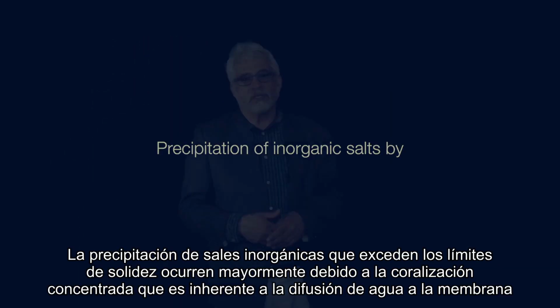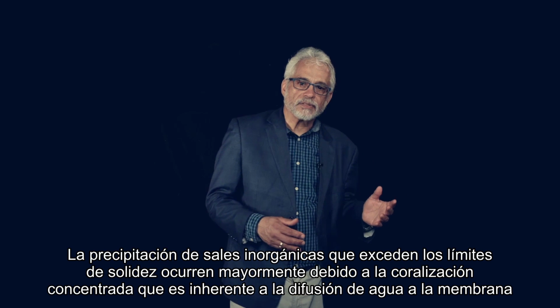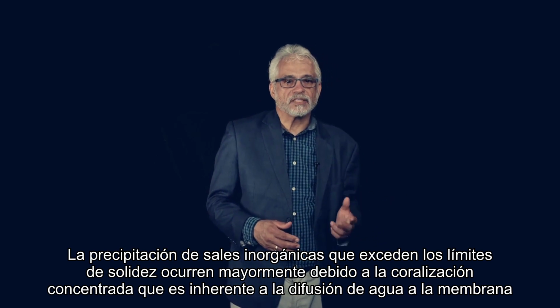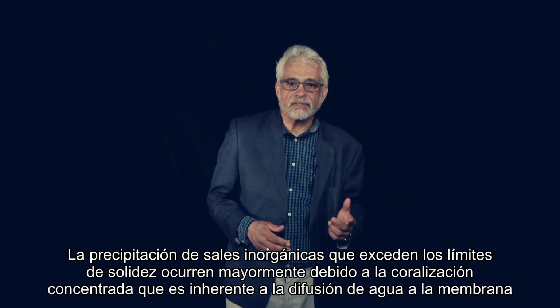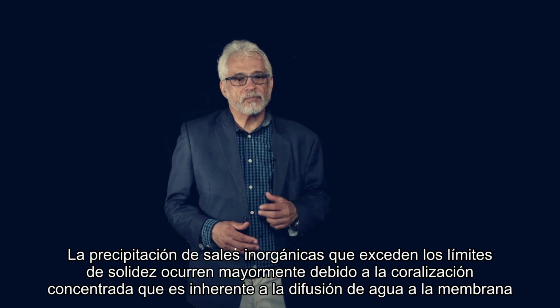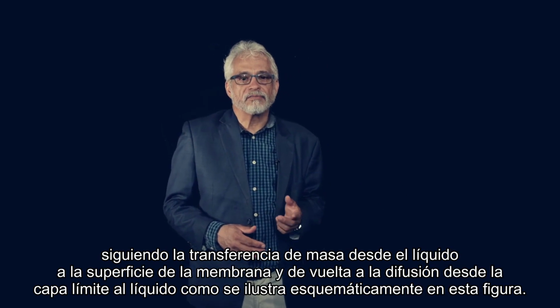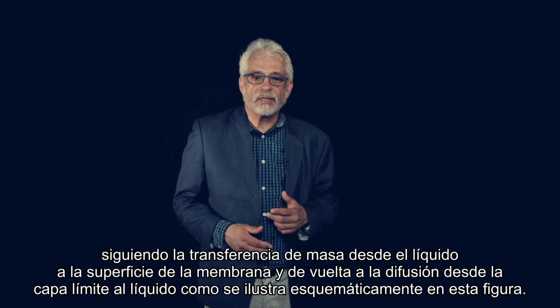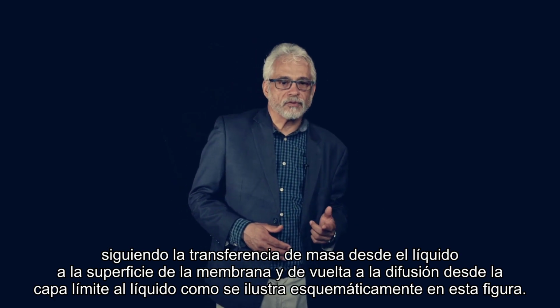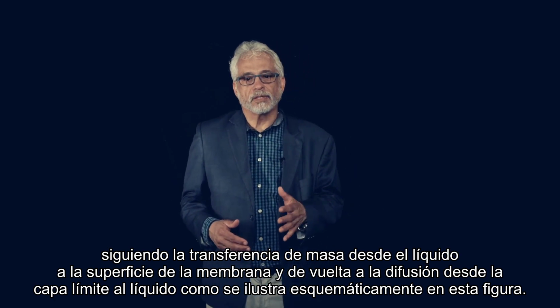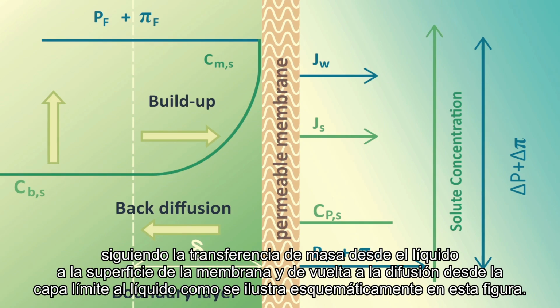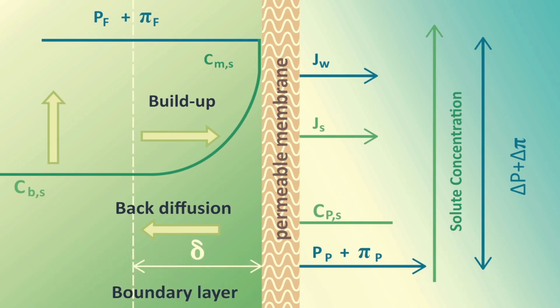Precipitation of inorganic salts by exceeding the solubility limits occurs mainly due to concentration polarization, which is inherent to the water diffusion through the membrane, following the convective mass transfer from the bulk to the membrane surface and back diffusion from the boundary layer toward the liquid bulk, as schematically illustrated in this figure.